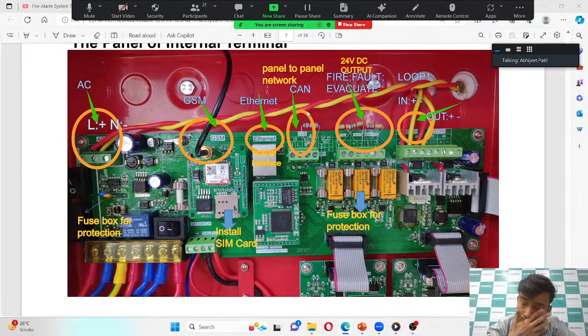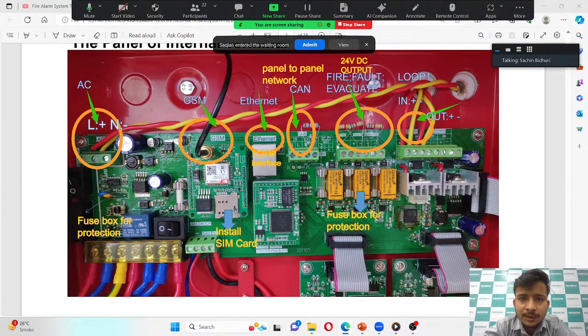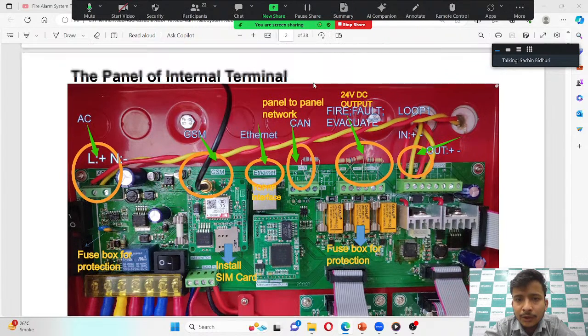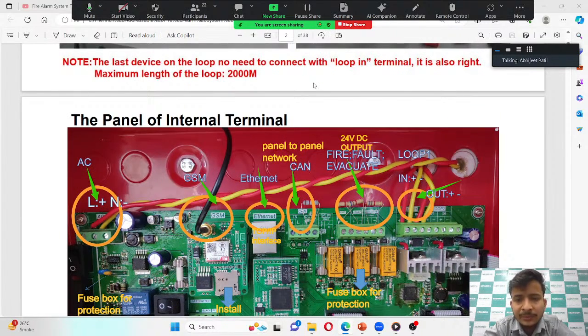Sir, if the length of the cable is extended beyond 2 kilometers, then what is the solution for that? For 250 devices, you just add those devices, there will be no issue. But for routers there is a limitation: you can connect a maximum of 40 routers in a loop, because the current consumption of a router is more than that of the detectors. If you are just adding 10 or 20 routers in a loop and you are going up to 2000 meters, then there is no issue. You don't need to add any external power supply or anything else. It will work normally.